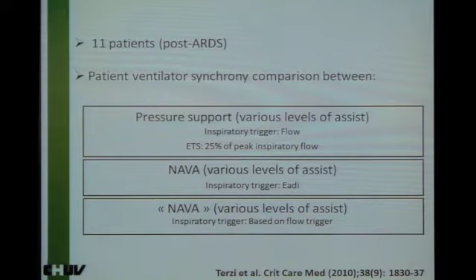They compared pressure support, NAVA as the whole concept, and NAVA with a high EADI trigger to inactivate the EADI-related trigger. And they found that the worst was pressure support, and the best was NAVA using both proportional assist ventilation and EADI to trigger the ventilator. And this is the answer. It's really both proportional ventilation and EADI trigger which can explain the improved synchrony we can observe with NAVA.